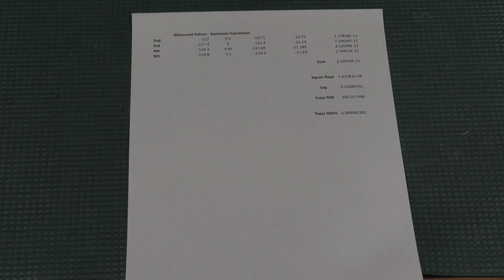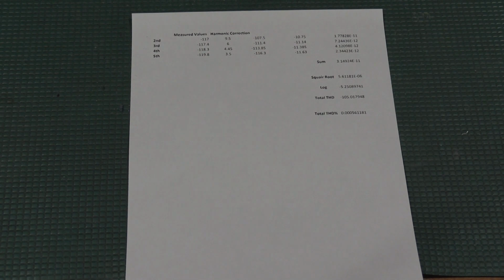The harmonic correction factor. This is because the calibration fixture is a 100% passive filter, so there is a little bit of a correction factor that needs to be applied. That comes out of the manual from 10 hertz to 20 kilohertz, essentially the audio range. These are the correction factors you would use. Above 50 kilohertz, there is a different set of correction factors, and above 100 kilohertz, there is yet another set of correction factors. That's just due to the physical properties of the notch filter.